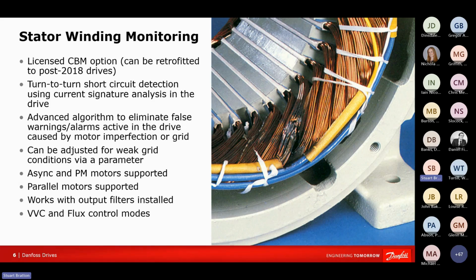The same sort of technology is also capable of detecting problems with sine filters. If you have a sine filter connected to the output of the drive, for example, in an installation with a long motor cable, such as a borehole pump, then a similar feature in our CBM suite can detect a problem with the sine filter. The capacitors, for example, starting to fail in a sine filter will result in a change in the current signature that the drive is producing.